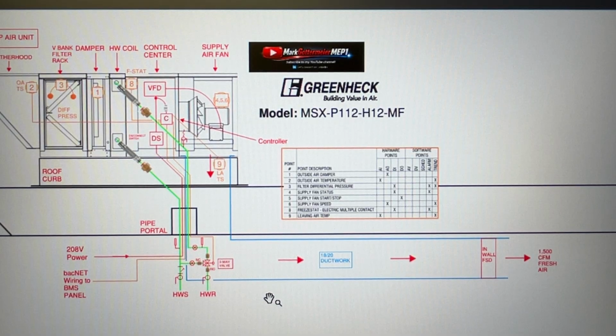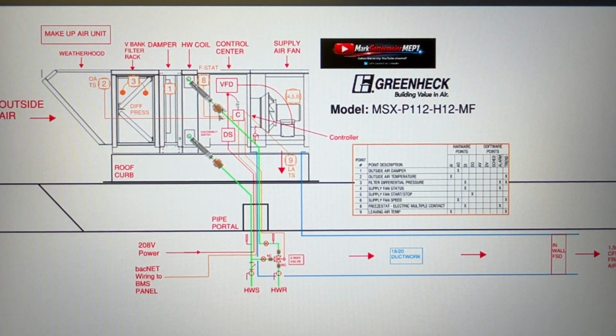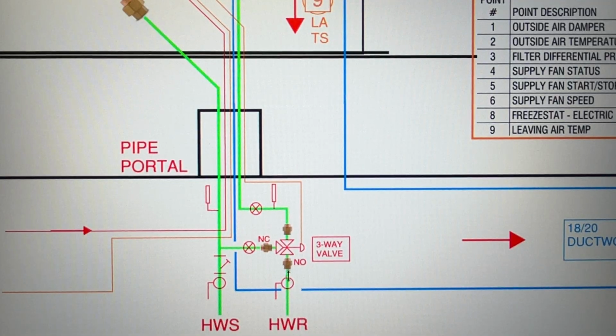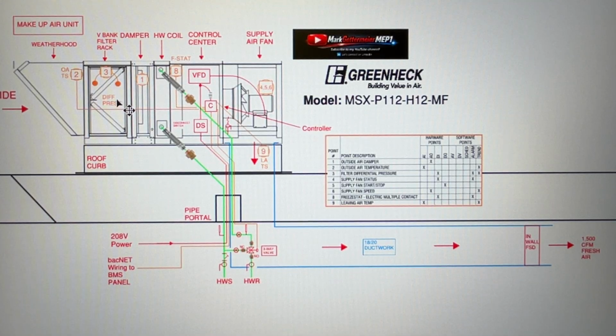So before, I talked about how the air coming in was treated across a hot water coil if we have to warm up the temperature of the outside air, because it's treating that apparatus bay like we talked about. There is a glycol system that's heated by boilers. There is a three-way valve here. So when it's trying to make up air for that apparatus bay, depending on what the outside air is, this three-way valve would allow glycol, as required, to go through the hot water coil, or it will just bypass it altogether.